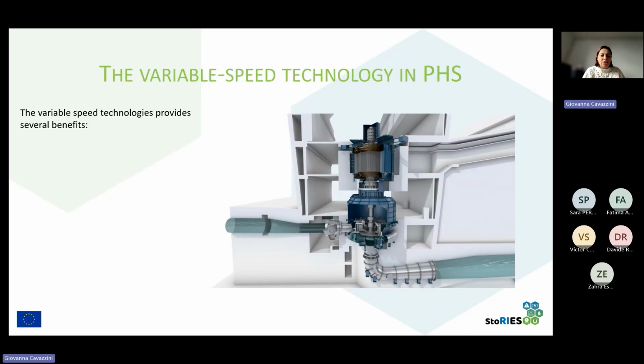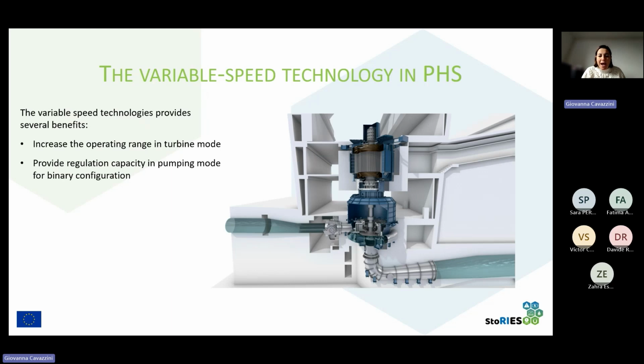The variable speed technology included in this new generation of pumped hydropower plants provides more than one benefit. In particular, it allows to increase the operating range in turbine mode in order to be able to generate power even at partial loads. It adds regulation capacity in pumping mode for binary configuration, because in the past the pump turbine had no regulation capacity in pumping mode. And it also allows to increase the efficiency in power production and in pumping mode when the power plant is required to regulate the frequency of the grid.